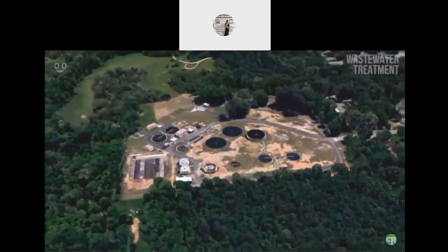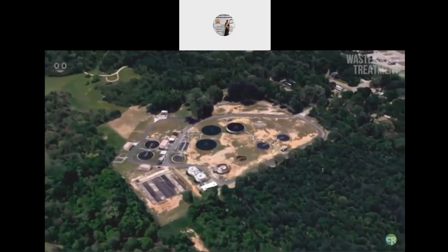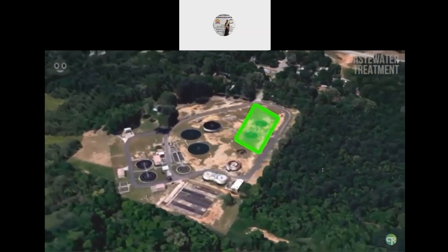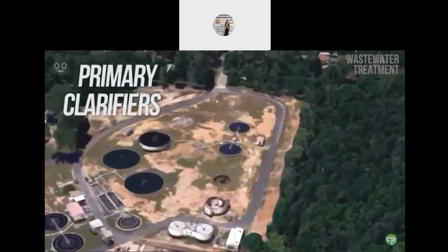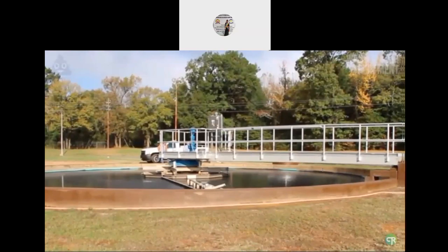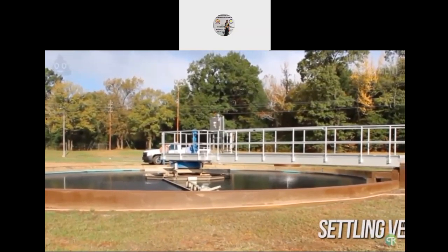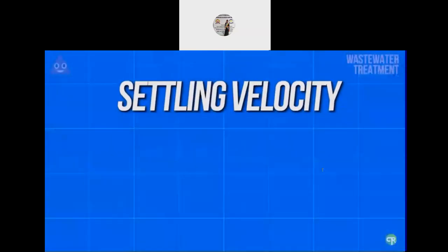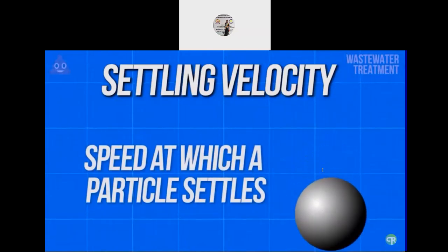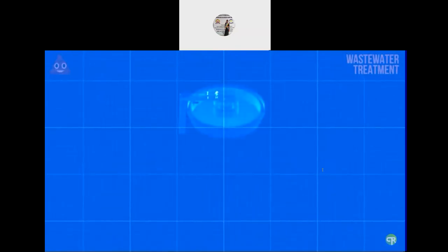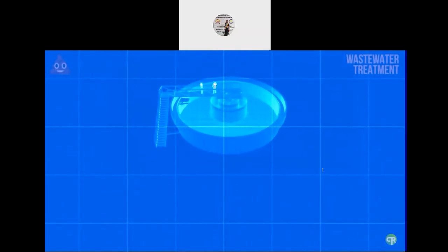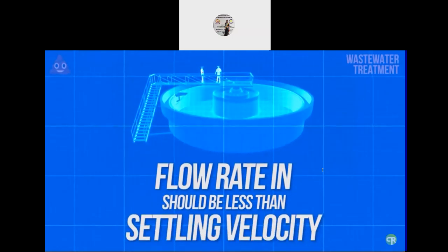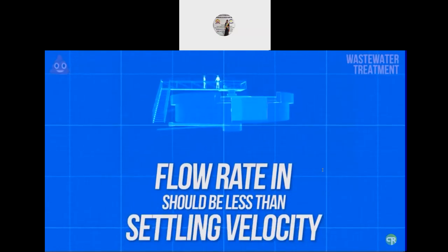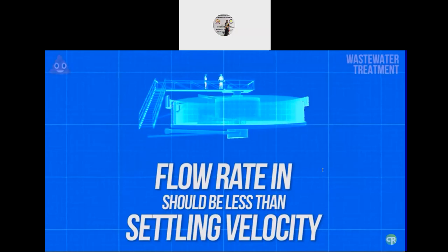Following the grit chambers, the sewage will move on to the primary treatment process, which starts with a large basin called a primary clarifier. Primary clarifiers and clarifiers in general function on the principle of settling velocity. This term can be defined simply as the speed at which a particle settles. For wastewater being pumped into clarifiers, it's important that the flow rate of the water being pumped in doesn't exceed the settling velocity of the particles trying to be removed.